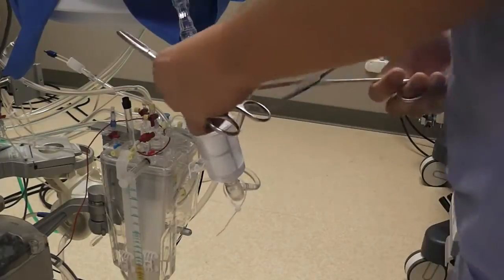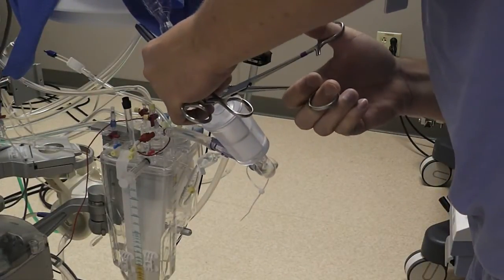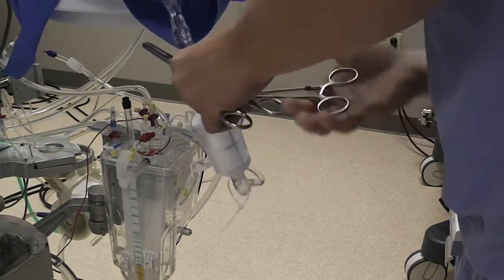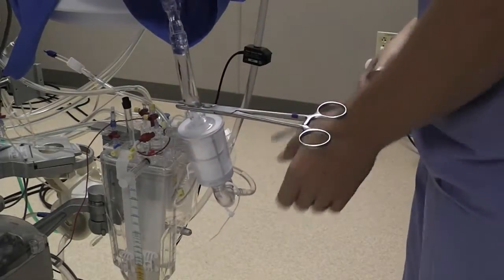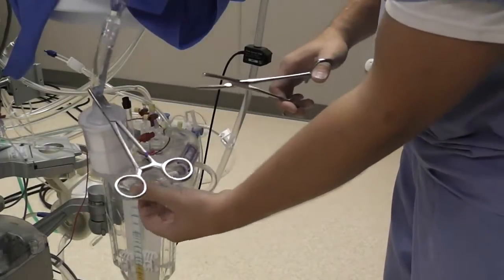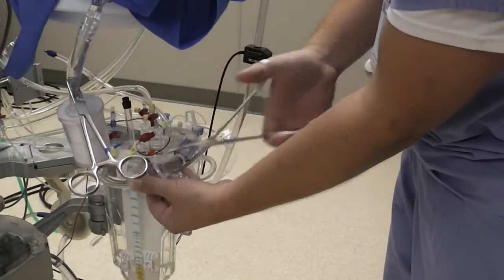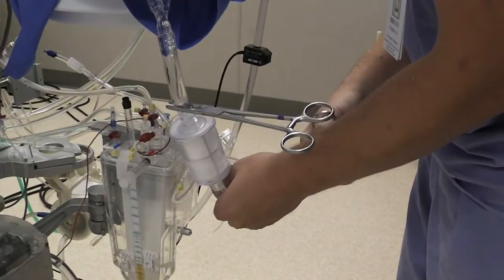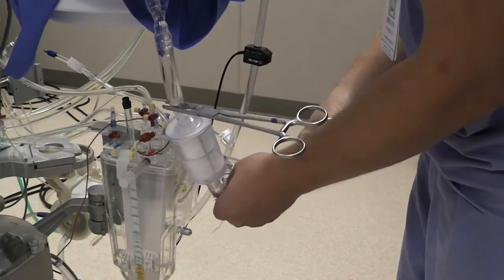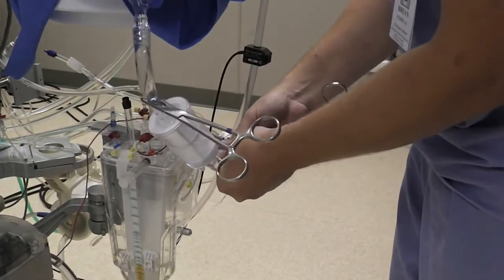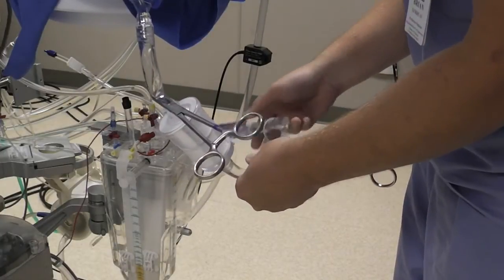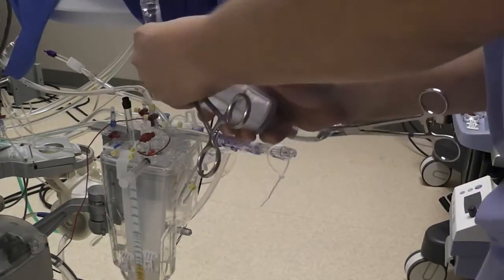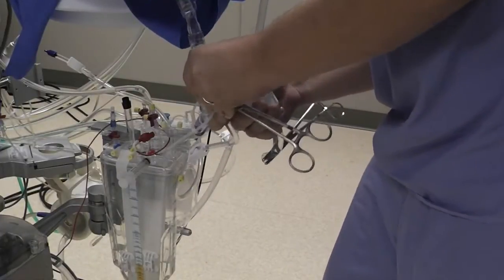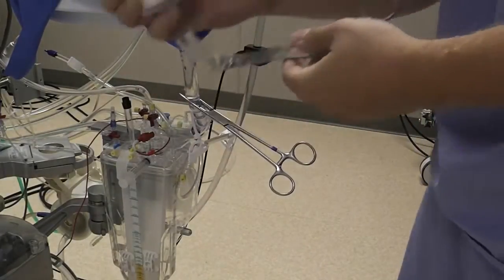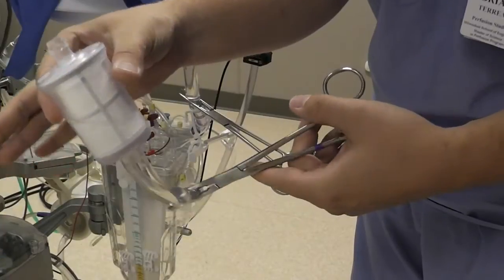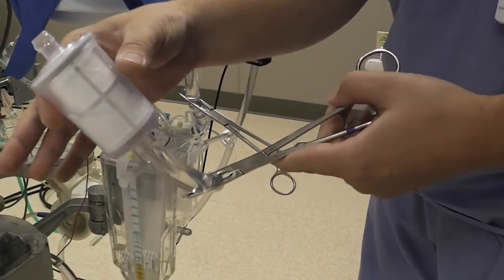You're going to need 2 clamps. Take one clamp above the pre-bypass filter first. Do that first. And then at the lower connection, right above or right below the pre-bypass filter, you're going to remove the bottom section. Kind of leave that tail in there for a second. Remove the top section. Now reconnect these. And this is the section of filter you're left with. You're going to go dump this out in the sink and make sure you don't leave it there.